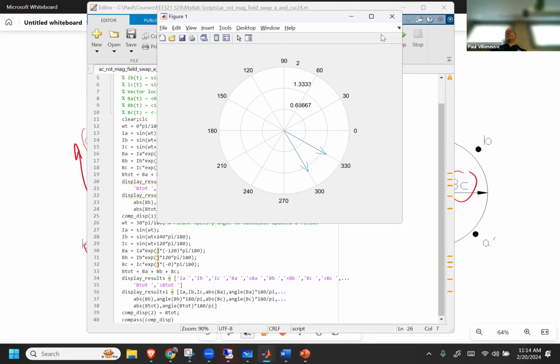This is a great thing, because that means I can make one motor, a 100 horsepower motor, and get it to rotate any way I want. You just have to change the field, or change the windings in the field, or not change the windings, change the connections in the field. And that's literally what you do in industry.